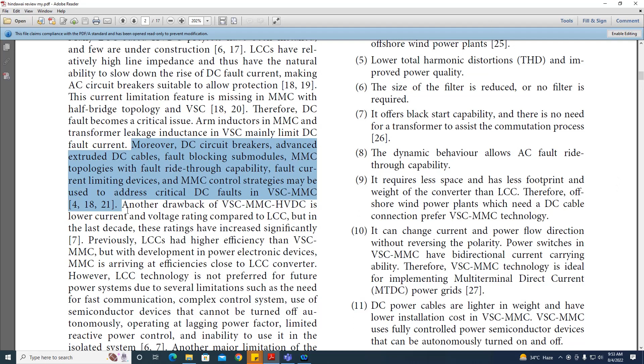All right. So DC fault ride-through is itself a very hard research topic going on in the research area of MMC HVDC. Another drawback of VSC MMC HVDC is lower current and voltage rating compared to LCC. But in the last decade, these ratings have increased significantly. Previously, LCC had higher efficiency than VSC MMC, but with developing power electronic devices, MMC is arriving at efficiency closer to LCC converter.